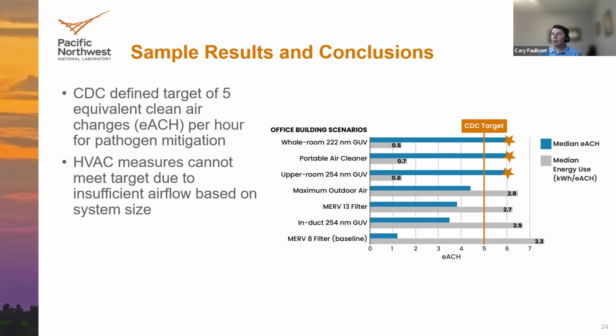And our key takeaway here was that the HVAC system measures, which include maximum outdoor air ventilation, MERV 13 filtration, and in-duct GUV, were unable to meet the CDC target for this office building. Not because they're not an effective way to clean air, but because of the system limitations on the HVAC system. Even if they're able to provide clean air, not enough airflow was able to be pushed through the HVAC system to the zones to meet that high 5 EACH target.